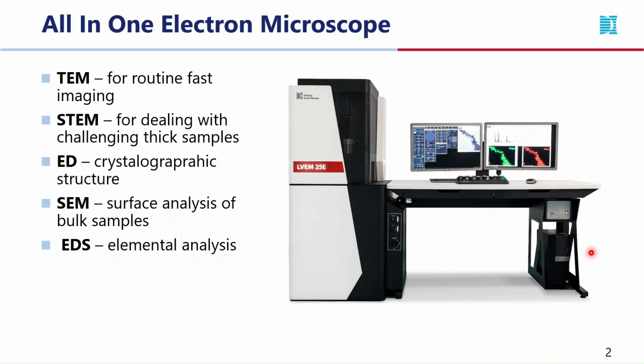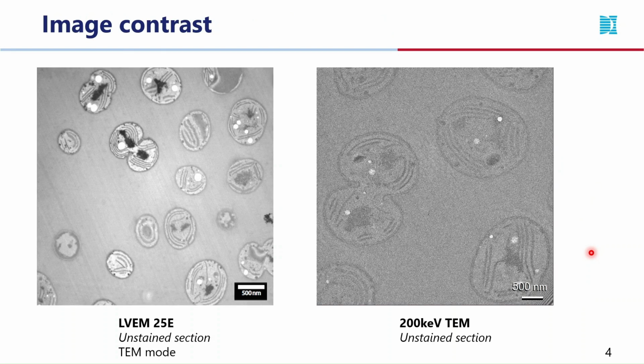The first question which should be answered is why should you prefer low voltage transmission microscope against the conventional ones? The most important advantage of our system is extraordinary image contrast. The lack of contrast is a well-known phenomenon in the case of transmission electron microscopy, but our low-voltage devices can provide great image contrast, even for the samples consisting of light elements, typically biological sections, where, for example, different organelles or membranes can be resolved with unprecedented contrast.